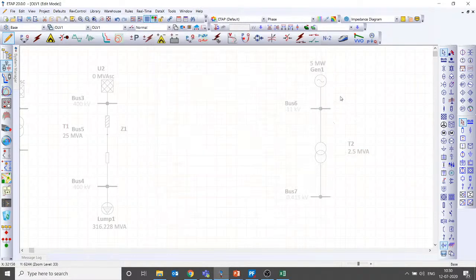If you keep it in MVAR control mode or power factor control mode, your system will not have any voltage regulating device. At least we need one device which is able to regulate the voltage and frequency in the system. We are not really accounting for frequency in load flow, because we assume the swing bus takes whatever the mismatch is, but at least one bus has to regulate the voltage. So a swing bus is mandatory. If you give voltage control mode and enable that option I showed in the tools options, it will automatically be taken as a swing bus and run. You cannot operate your generator in MVAR control mode or power factor control mode.